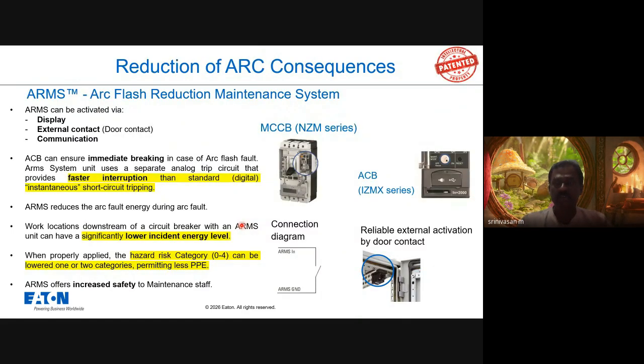Also, we have the ARMS protection, the arc reduction maintenance system. What we have seen earlier, Arcon, is for arc mitigation at the switchboard level for the entire switchboard system. At the breaker level, we also have an optional feature called ARMS protection. Suppose you have one switchboard with one particular outgoing feeder feeding one load, for example a chiller. If you are doing some maintenance work on the cable from the breaker to the chiller under live conditions, we don't recommend doing any maintenance on live switchgear, but in some exceptional cases with critical applications, we have to do maintenance on the live switchboard system.